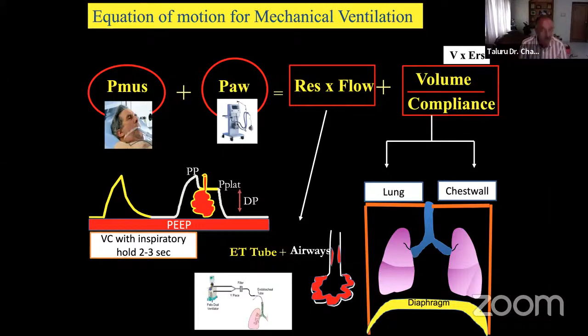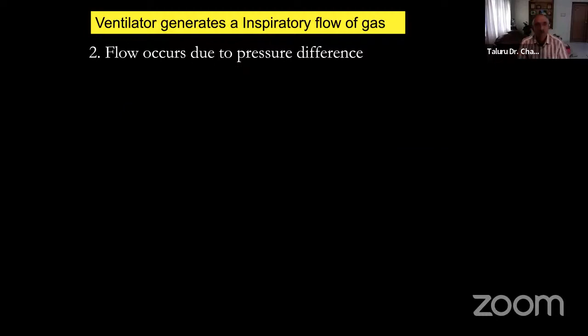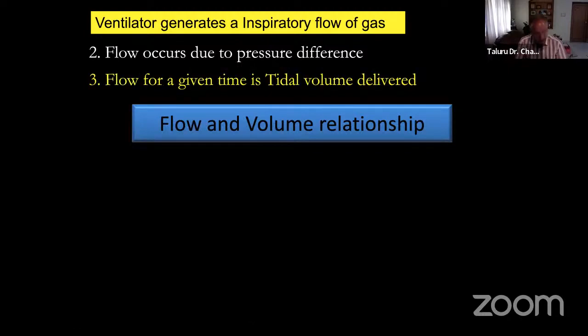I said in the last session also that the ventilator generates just the inspiratory flow of gas. It doesn't do anything other than that. And flow occurs only when there is a pressure difference. Flow for a given time is the tidal volume delivered, and I have already shown you this. So you can alter the delivery of tidal volume by increasing the peak inspiratory flow or increasing the time.